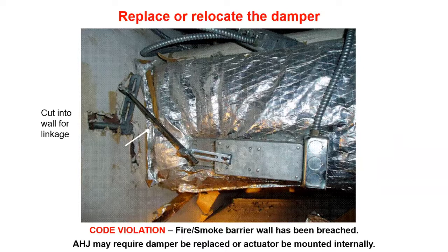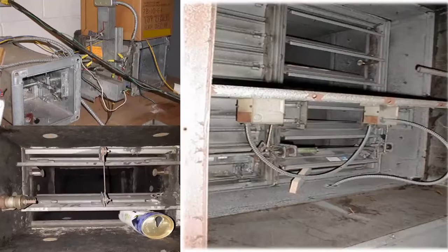When examining some of these jobs, it's amazing that it got passed to begin with. The whole purpose of drywall, there on the left side of the picture, is to protect. That's a rated wall. You can't go cutting the drywall out like that. So in a case like this, you've got to relocate the damper outside of the wall. I'd install a new damper. This is really old and beat up. You could put sheet metal behind that damper shaft, but it's pretty tricky to get it in. But this is definitely a code violation. I've gotten 20 variations of this picture sent to me over the years. We see a lot of dampers installed wrong. And this is something where a sheet metal contractor can come in and replace that damper, and then they can seal up that drywall.